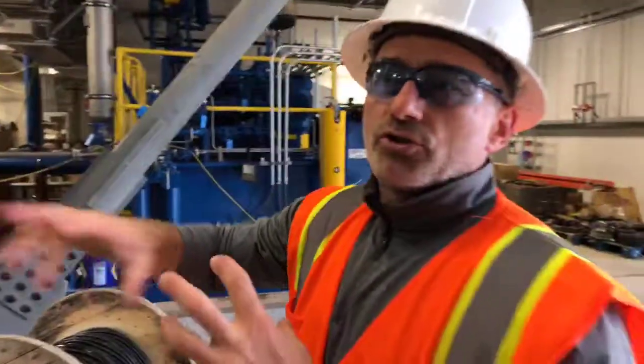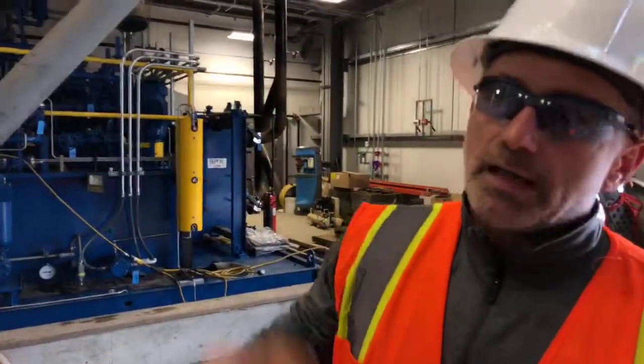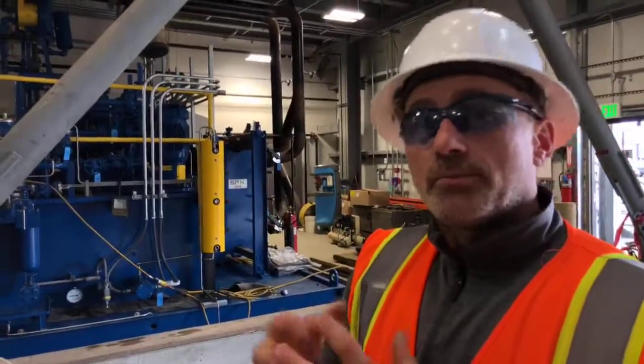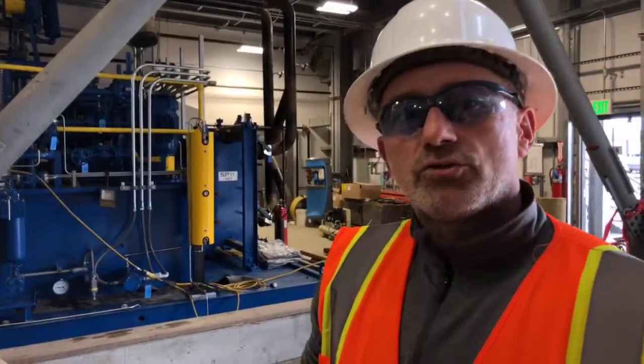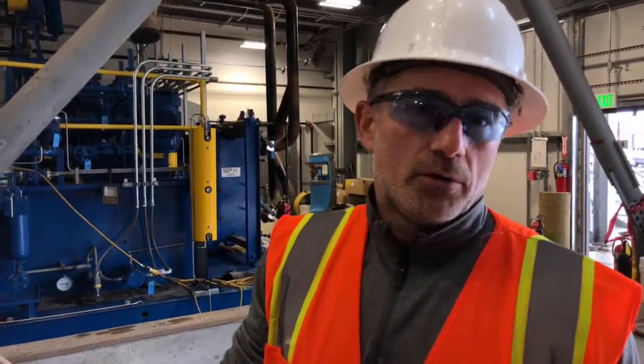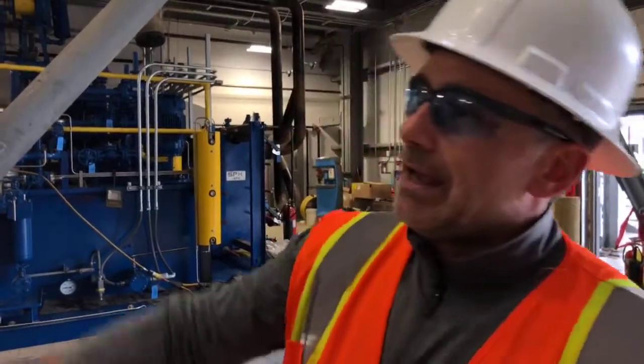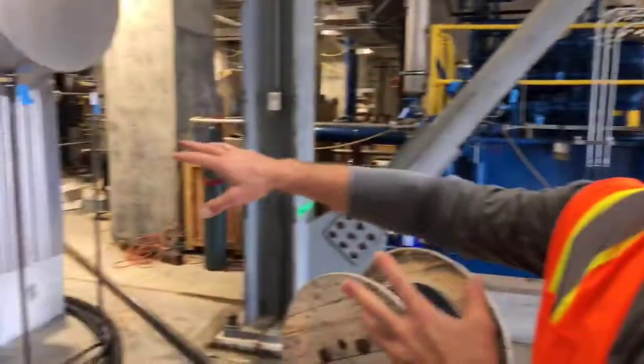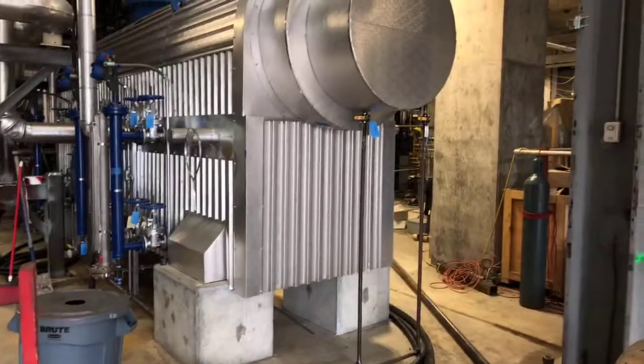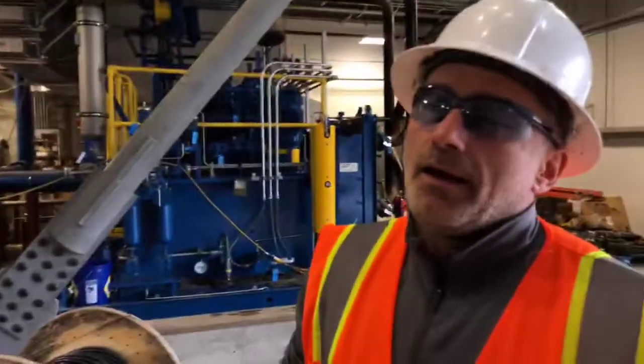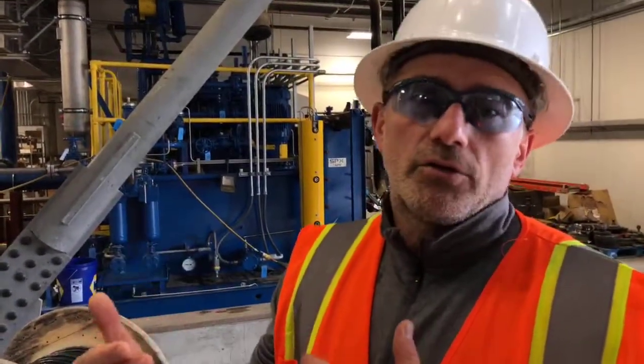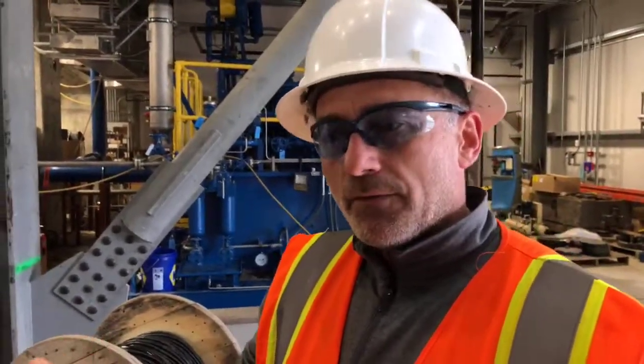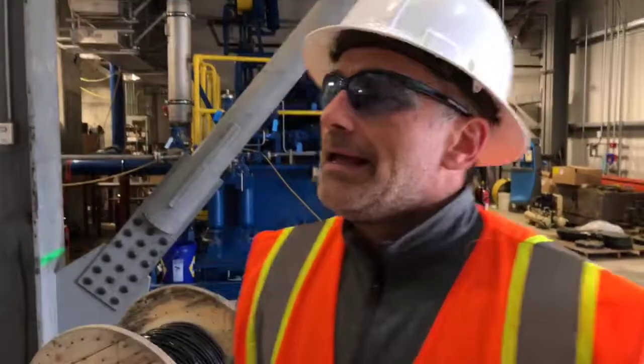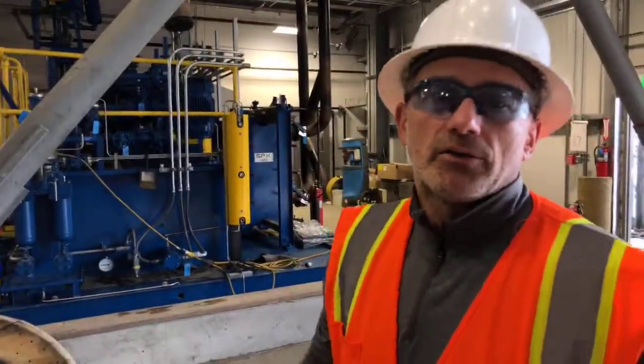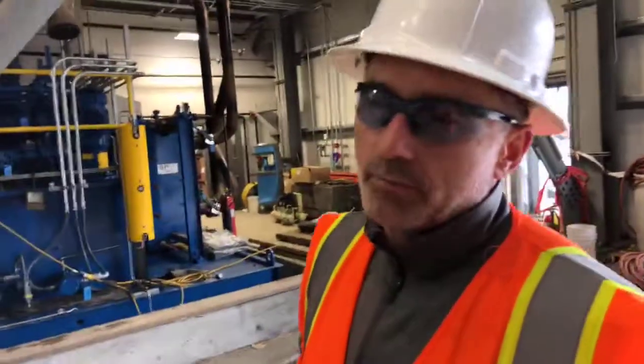In summer we use chilled water from the chillers down in the power plant to keep the buildings cooler. In winter we don't use the chillers, but we have the loop available, so we isolate the chillers and run water through this instead. We warm up the water and send that low energy, low heat water to the preheating coils, which helps preheat the air from maybe minus 40 up to 20, just adding a bit of ambient heat to the system. It's basically free energy, well, not entirely free since you still have to pay for the pump.